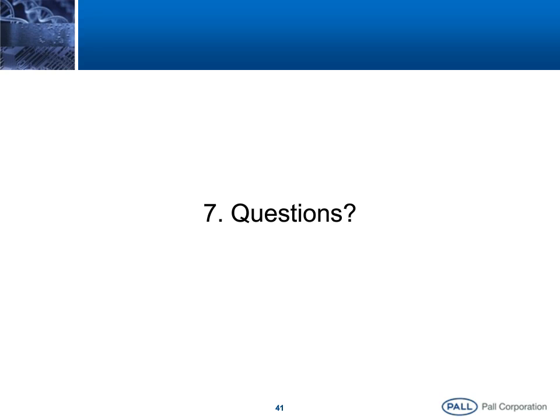And we've got a question from Greg. How can you evaluate rental skid performance when installed? An important question when you want to be able to monitor what sort of efficiency you are getting. What we will do in that case is bring forward our scientific and laboratory services, or SLS, team. They will perform tests such as gravimetric analyses to establish parts per million solids levels upstream and downstream of the filter. They can perform tests such as Gammon Aquaglo tests to quantify free water levels upstream and downstream of the unit. And a range of other tests are available as well, depending on your specific requirements.